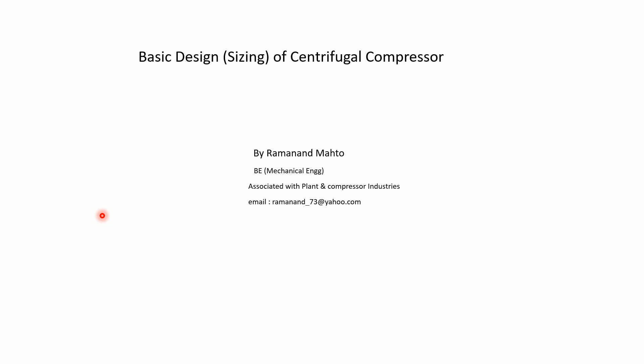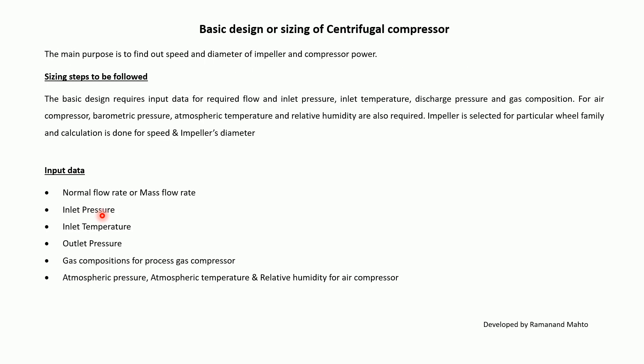Today we'll discuss basic design and sizing of centrifugal compressors. The main purpose of sizing centrifugal compressors is to find out the diameter of the impeller and the power of the compressor. The basic design requires input data for the required flow, inlet pressure, inlet temperature, discharge pressure, and gas composition. For air compressors, barometric pressure, atmospheric temperature, and relative humidity are required. An impeller is selected for a particular wheel family and calculations are done for the speed and diameter.